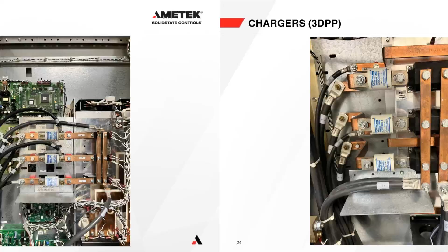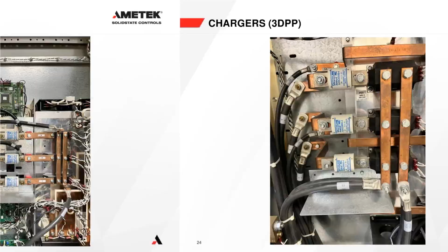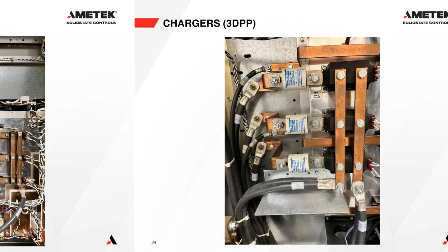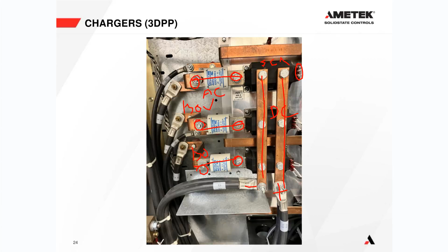So that's in our single phase system, and it's even easier to see on our 30 kVA three-phase system. Remember, when I say single phase and three phase, I'm talking about the output of the UPS - our rectifier bridges are all the same, we use three phase in. So once again, we've got 130 volts AC going in through to this terminal. That goes into the black SCR, mounted here, and then once again we have positive and negative coming out - this one is our negative, this one is our positive. So AC going in, DC coming out, simple as that. And once again you can see these connections to the SCRs, that is the gate drive signal to the SCRs.